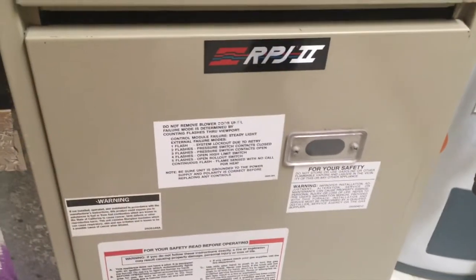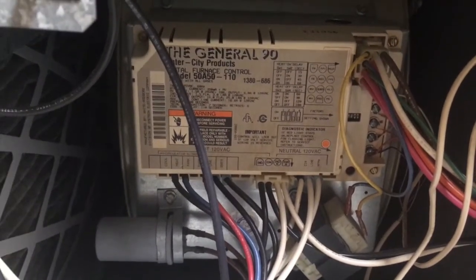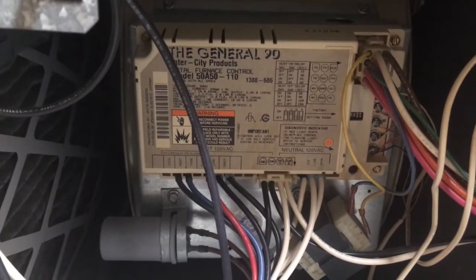So it looks like cleaning the flame sensor fixed the problem, but if you're finding that it doesn't fix your problem, it could be the controller too, so I'm going to show you where that's at. I'm going to make sure my power is off before removing any covers, and the controller is just going to be under the lower of the 2 covers. So I'm going to remove that, just pull up and then out. And there's the controller for this furnace. That looks like the original controller.